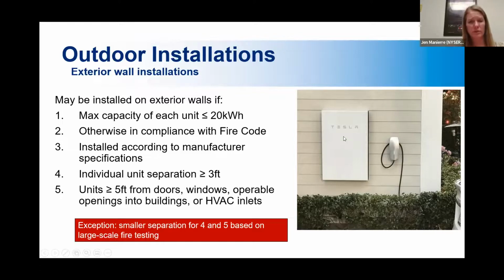If you're going to hang more than one unit, they need to be separated by at least 3 feet. That's the protection so that if something does go wrong with one, it's not going to propagate to the one next to it, because 3 feet is enough space to not allow it to propagate. And then finally, they need to be at least 5 feet from doors, windows, any openings or HVAC inlets into the building, because if that does start to off gas or if it does catch fire, you don't want the gas going into the building or the flames licking into it too. So separated from each other and separated from basically any inlets to the building.